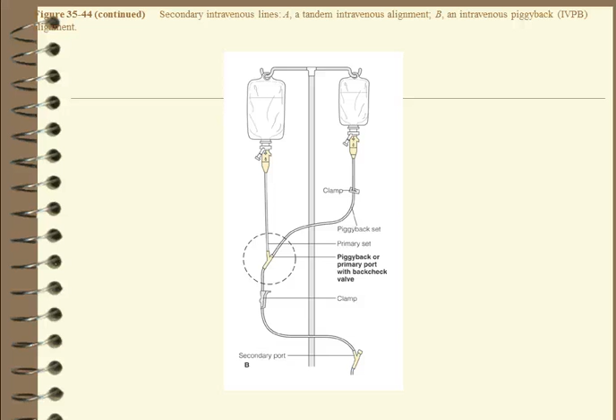The flow is related directly to the height of the liquid column. It's related directly to the diameter of the tube's lumen. So if you've got a wider lumen, it's going to go in faster. If you've got a narrow lumen, it's going to go in slower. Go back up to the flow related to the height of the liquid. If you've got the bag up high, it's going to go in faster. If you lower it down close to the patient, it's going to go in slower. And if you lower it lower, it's going to stop going in, and then it's actually going to back up if you put it too low. So that's why they're always holding the bag over the patient when you see them in the movies.